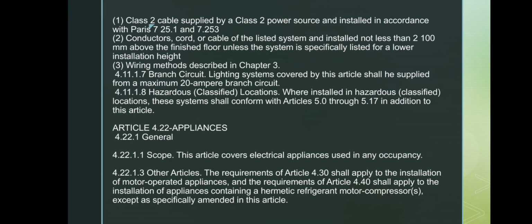Next, acceptable wiring methods. The wiring used may be Class 2 cables, properly rated cords or conductors installed high enough above the floor, or any Chapter 3 wiring method. Lighting systems under this article must be supplied only from a 20-ampere branch circuit.